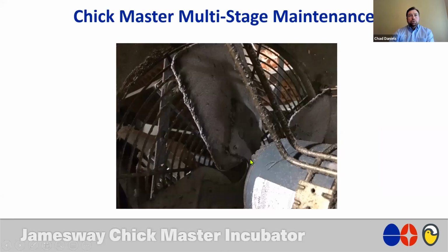If you get a little bit of a closer look at this, you can see the fact that this is the cutting edge of your blade. And as the fan rotates, this essentially cuts into the air and forces it down through the fan guard. And so when you have this volume of dirt buildup here, that fan's not going to do that very efficiently, not going to create very good static.